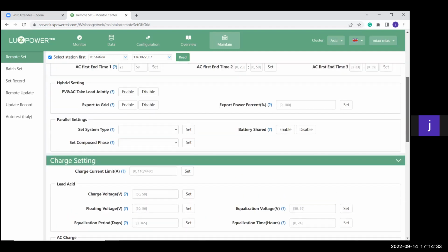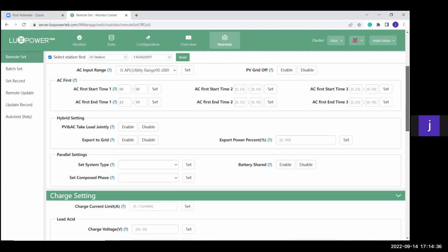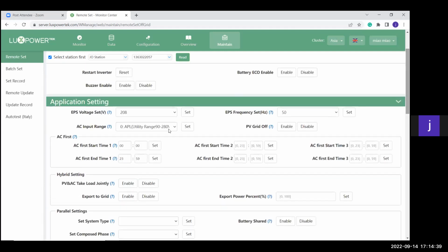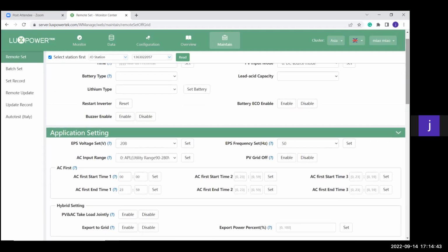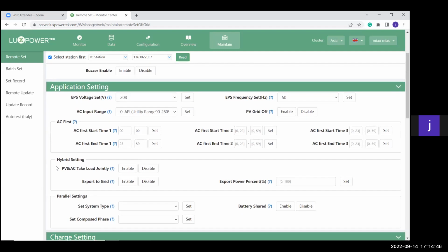Now let's say, for instance, I have a system where I want to use solar, then utility, and then battery. Then all of this will be the same, except the only change you're going to have to make is the PV and AC jointly function. You enable this function, and then the machine will use all available PV power with Eskom power as far as possible, and then just go over to Eskom as soon as your PV is no longer sufficient or no longer there to provide the load. With this function, if there is a 2 kilowatt load and your panels provide only 1 kilowatt, it will use 1 kilowatt from your panels and 1 kilowatt from the grid combined to provide the 2 kilowatt load.